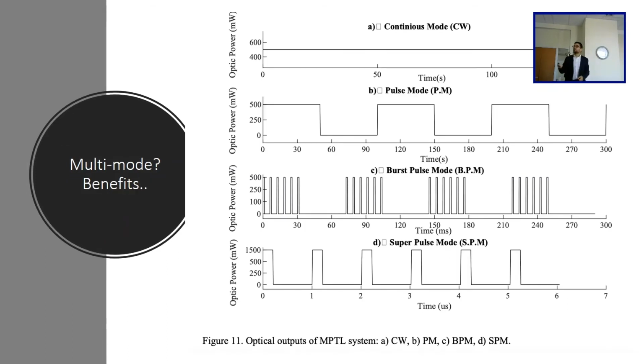And what are the modes? Why is it multi-mode? Why do we need it? There are 4 modes in our case. The first one is continuous mode. So you turn on the light and just wait there. The second one is pulse mode, so you're creating PWM signals. And this is burst pulse mode, in which within these pulses you have other pulses, which is the burst. And then this is super pulse mode. Just check the scale again. This is seconds, this is milliseconds, this is microseconds.